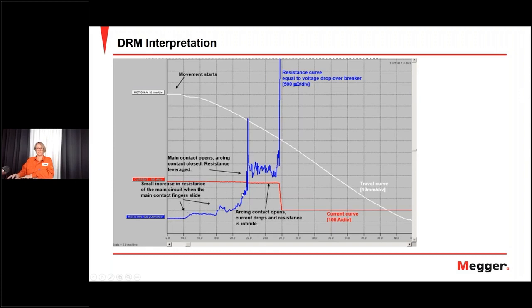So if you get changes here, this is mainly because of things like springs on the main contact, the pressure, and maybe dirt on the contact. Well, if this one is changing, that's a matter of the arcing contact having changed. And the biggest trouble is when this is starting to get shorter. So the breaker all of a sudden opens earlier, and you see that this is getting closer and closer to where the main contact is in the circuit.